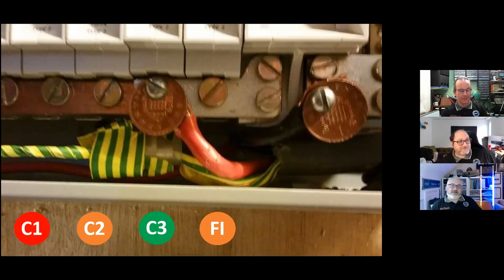Yeah, no, I agree. You could, yeah, definitely. Connection methods incorrect, not in line with manufacturer's assembly. There's many things that would come up with a C2. What would be happening for you to elevate that to a C1? Definitely signs of thermal damage, loose connections, damage to the bus bar, any visible cracks or splits in the copper or conductor material, thermal damage to the breakers above, black or soot deposits.